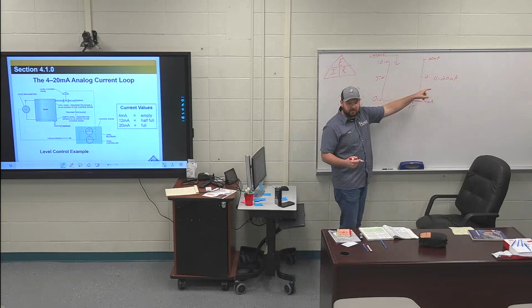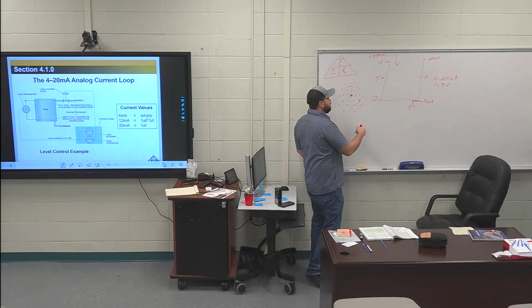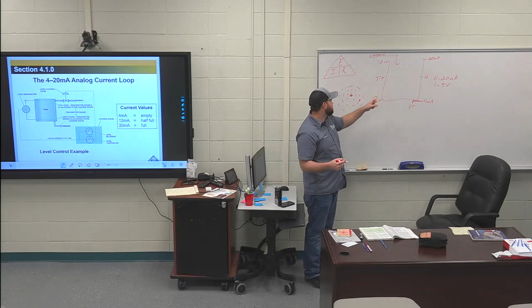If I have a piece of instrumentation like signal wiring, and I put that somewhere right here, and I don't have any shielding on it, that electromagnetic interference is going to interfere with that signal. Because my signals are small, like 4 to 20 milliamp or 1 to 5 volt. Like those are small voltages. So if I induce a voltage on that wire, that's bad, right? Especially if I have big power cables, that's a lot of EMI. Does that make sense? So what you do is you put a shielding around that cable, which just looks like a metal jacket, and then you terminate it on one end, and that drops all your electromagnetic interference to the ground. So you shield instrumentation cables to prevent electromagnetic interference. Good?